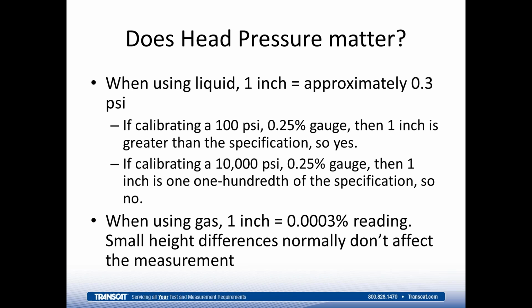Conversely, if we're calibrating a 10,000 psi gauge, a relatively high pressure, with that same 0.25% specification, well, now 0.3 psi is 1/100th of the specification. So it's not going to necessarily impact our measurement. So there'll be situations where we'll need to account for it, and there's situations where an approximation is sufficient, where we can look at the two gauges and say, yeah, they're close enough in height. With head pressure, we can calculate it and we can correct for it relatively easily. As I said, it's the height times density times gravity. We can also handle it by simply making sure that our device under test and our reference gauge are at the same height.